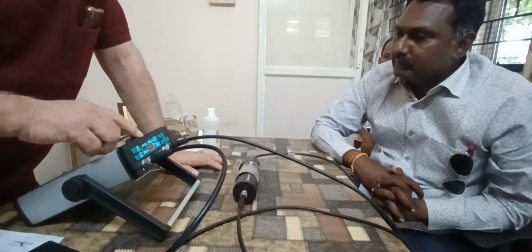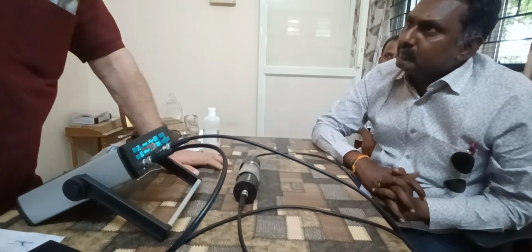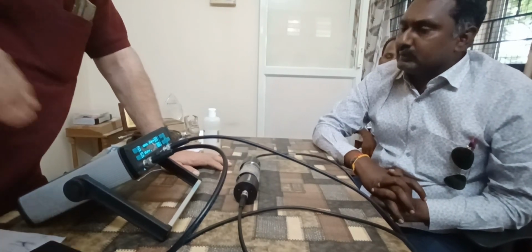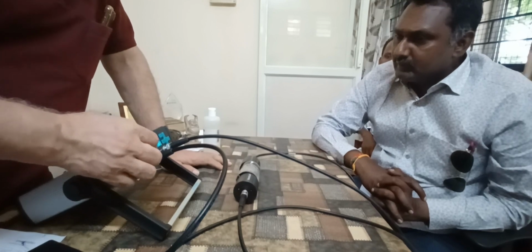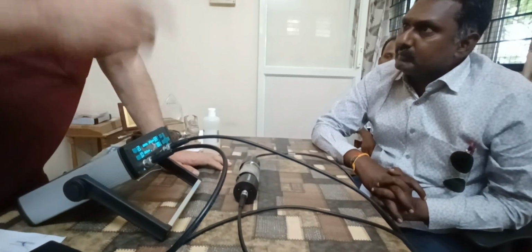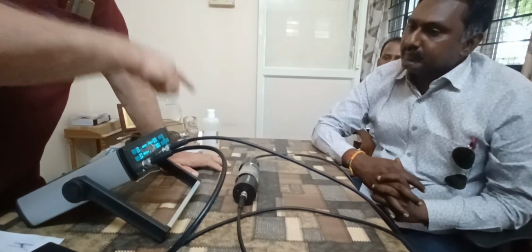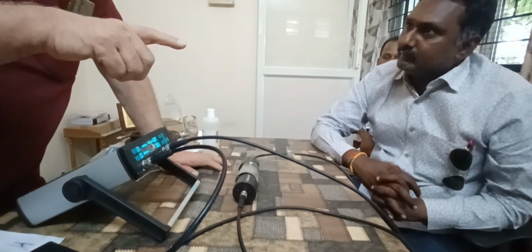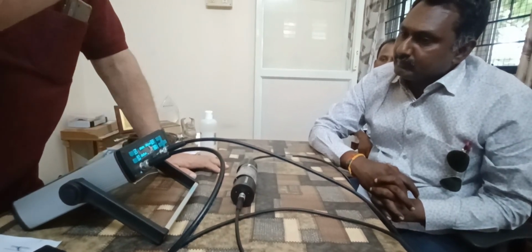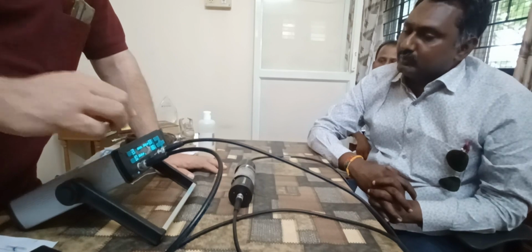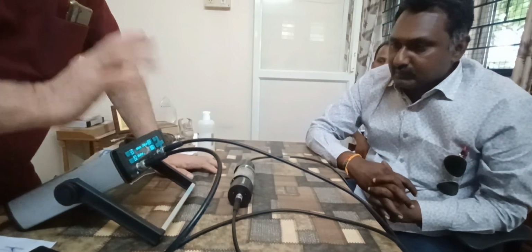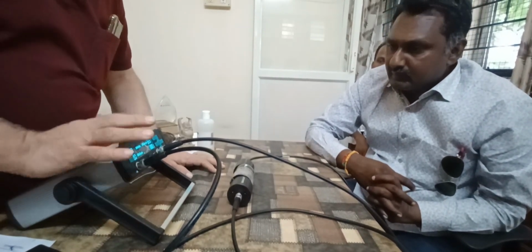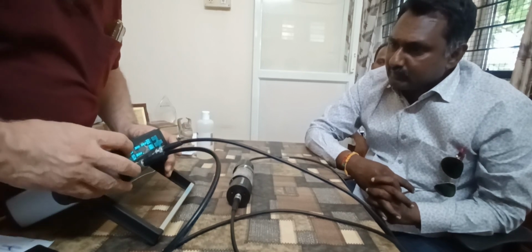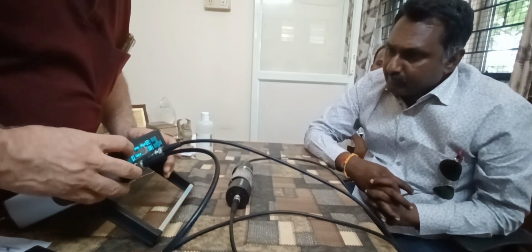At 24, you can go for lengthier testing. Each pulse will take 20.8 microseconds, and for 54 it is taking 9.3. So here it goes much slower, 20.8 microseconds. These are all default settings. I will go to 54.